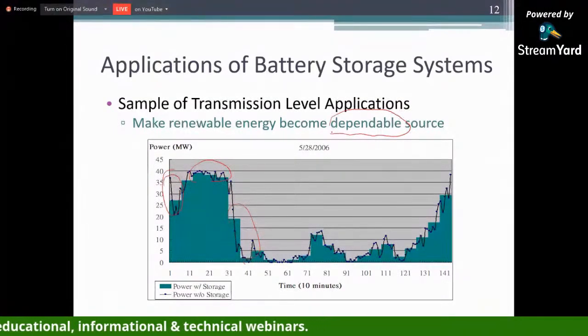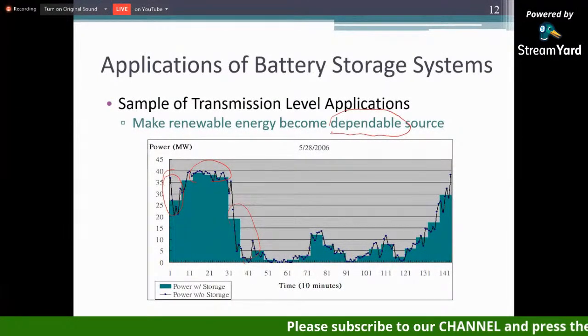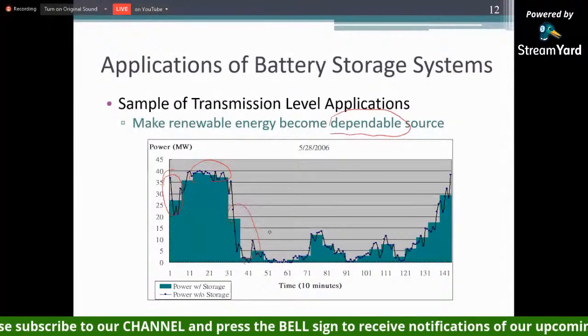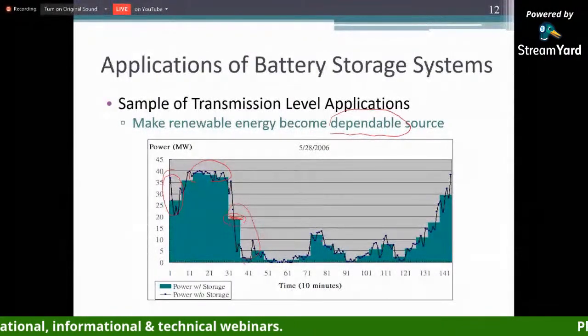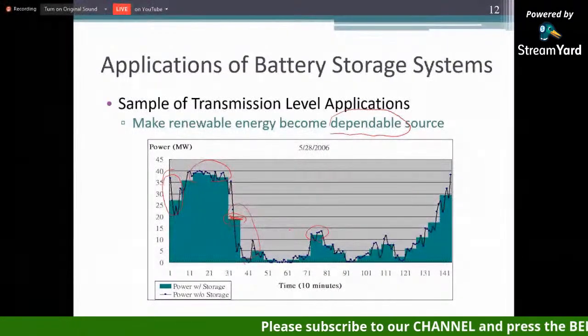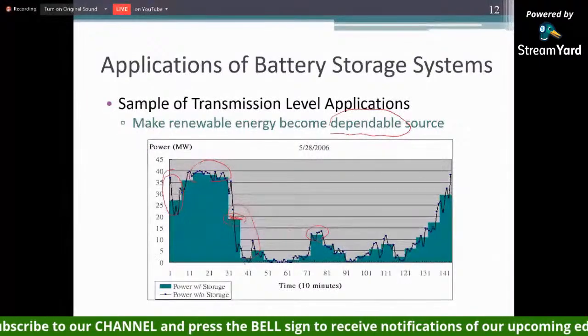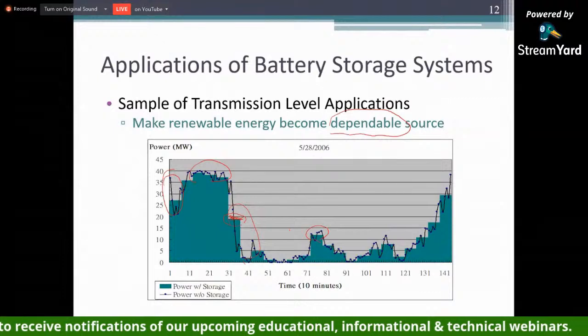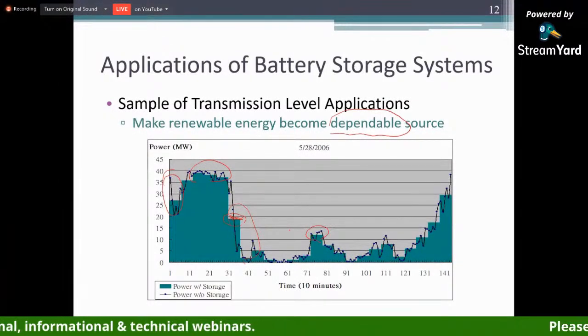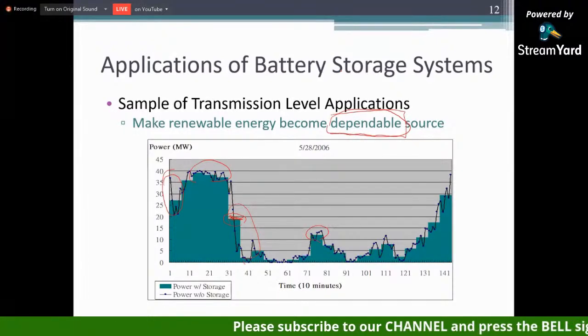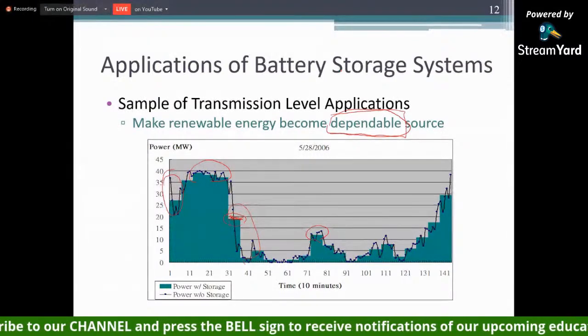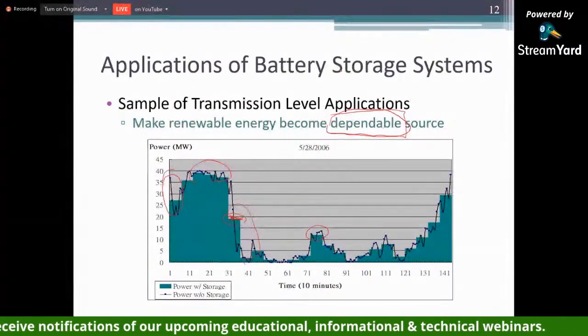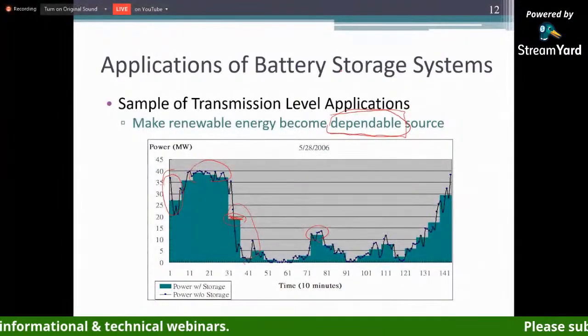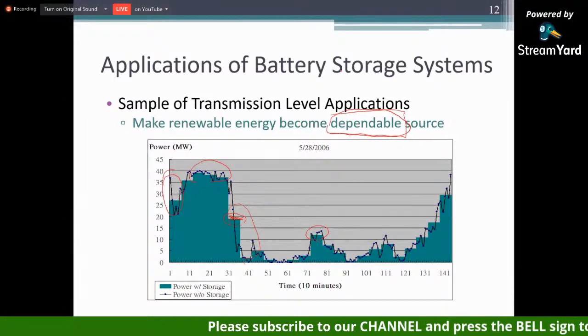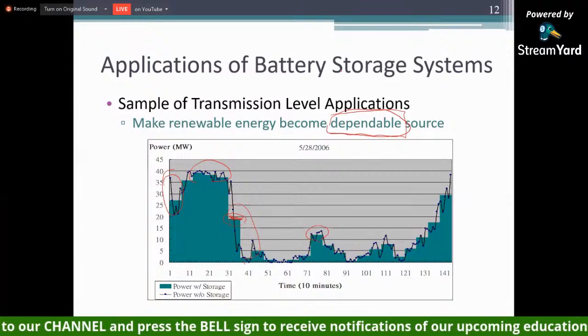So if the wind generation incorporates with the battery storage system, they will be able to tell for the next 15 cycles that they can give a fixed output. Basically, depending on the size of your battery and the wind quality, you will be able to tell the system operator for the next 15 or 30 minutes, 'I can give you this amount.' So you turn the intermittence into a dependable source. The operator can then consider that part of the generation dependable, and when they do the economic dispatch, they can exclude it and count it as a dependable source. This is very beneficial for system operation.